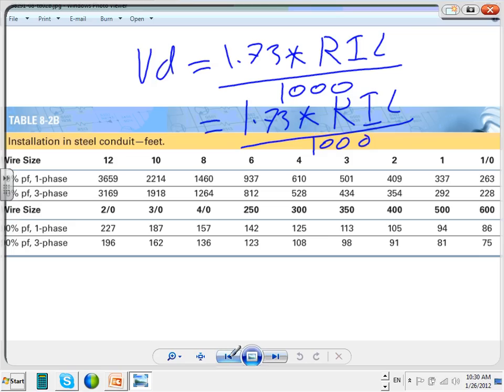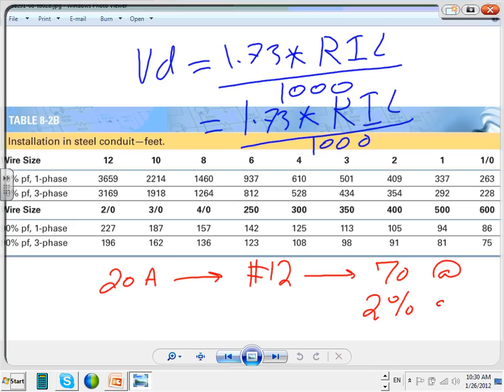So take this. If I have a 20 amp load and the conductor is number 12, I can push that conductor 70 feet at 2% voltage drop and at a voltage of 240. So the table tells you how far you can put your loads away based on a voltage drop of 2%. Why 2%? Branch circuits are always 2%, and 3% for feeders. Okay?